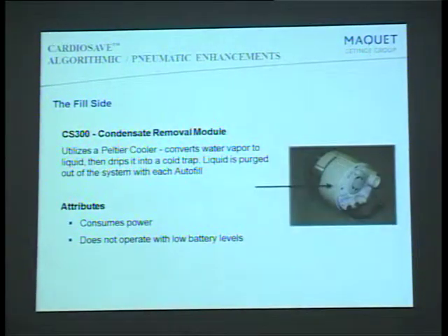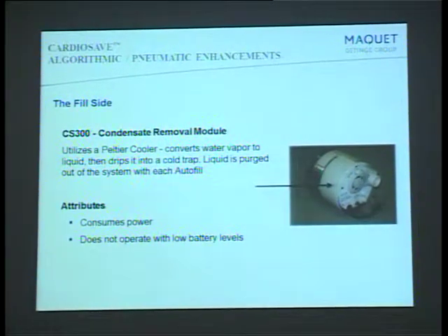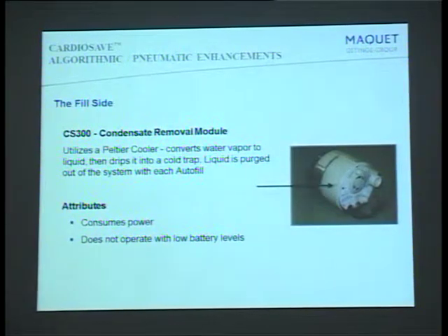There is something called the condensate removal module. Helium is a gas, and water vapor needs to be removed, otherwise it's going to dilute your helium. So you have a module called the condensate removal module. It uses a Peltier cooler, converts the water vapor into liquid, then it drips into the cold trap.